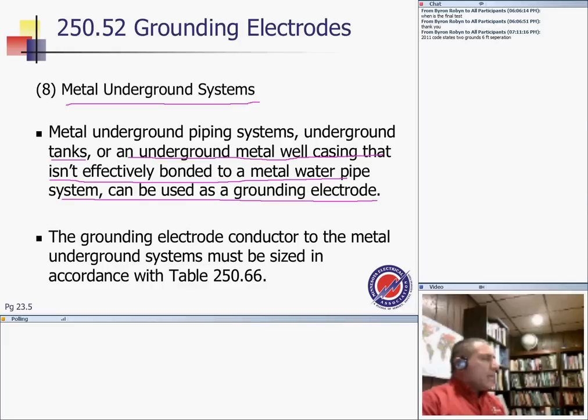So you take one of these metal buses and you bury that baby underground, I guess. If it's made of steel and you tie to it, that will probably qualify under certain circumstances as a grounding electrode system. Okay, metal underground must be sized, and all the sizes are based on 250.66. When we size, guys, we go to 250.66. How many of you have used 250.66?